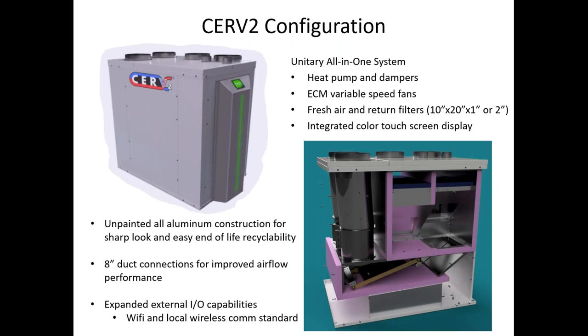The configuration of the CERV is a unitary all-in-one system. So the heat pump is fully contained in this box. There's not an indoor and an outdoor unit like you see for split systems. The fans are ECM variable speed. The filters are standard 10 by 20 inch filters. The display is an integrated touchscreen display on the unit. It's unpainted aluminum construction for a sleek look and recyclability. The duct connections are all 8-inch connections, as I mentioned, for having good airflow at low fan power. And then the CERV2 is the second generation unit with expanded capabilities for inputs and outputs and that external communication.